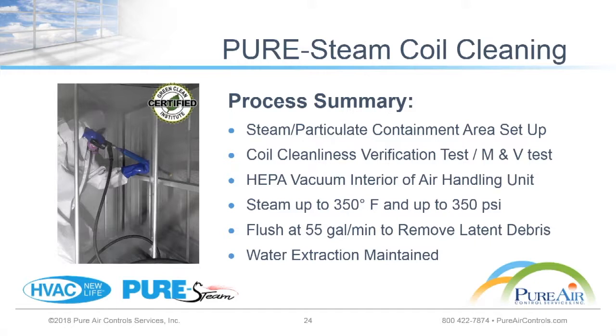So when we get ready to steam this air handler unit, and it's not just coil cleaning, but the real magic happens on and within the coils using this process, we set up a steam and particulate containment area. Being IAQ focused, if we're working inside mechanical rooms inside a building, we're trying to make sure that temperature and humidity within that building is regulated. So we don't need this moist, humid steam coming out of the mechanical room and billowing down the halls and affecting carpet and ceiling tiles and furnishings. So we set up a containment area, and that also keeps any particulate that's coming off the unit when we're steam cleaning it.